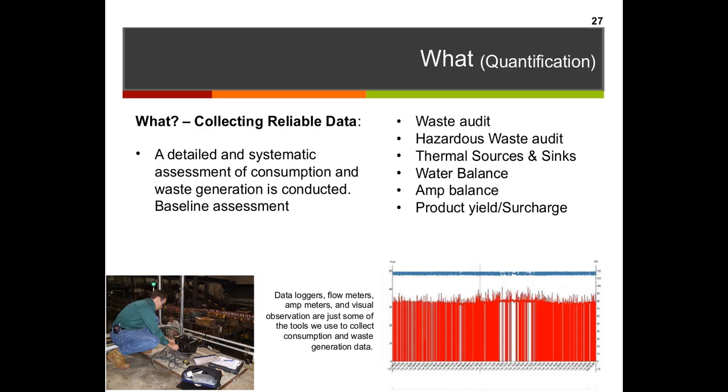it's a food processor. When we did our study, they're actually paying 3 times more on their water bills than they're actually using, right? So we put our meter next to the city water meter, and they agreed with each other, they're fine. But when we compared their own meter from the city with the meter readings on their water bills, they're off by 10 times. And so one of their meters was 10 times too high, the other one was 10 times too low. And the net effect was 3 times more water. So they're paying 3 times more for the last 2 years than they should have been.